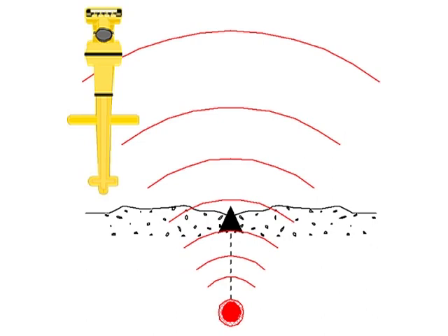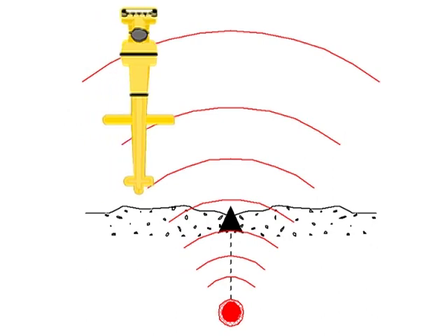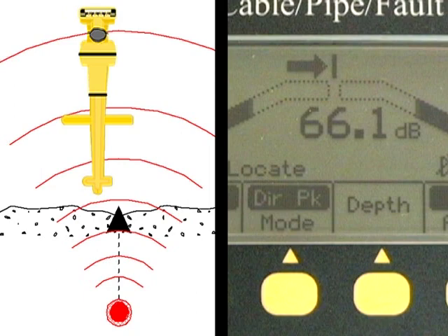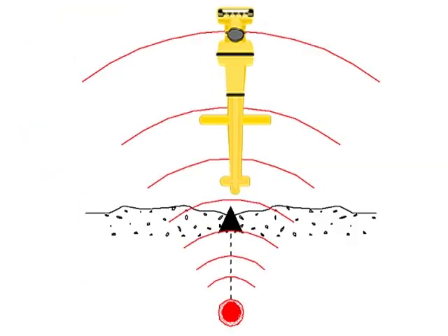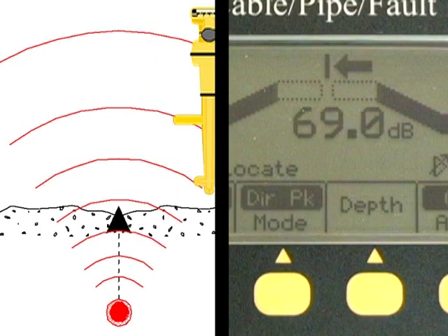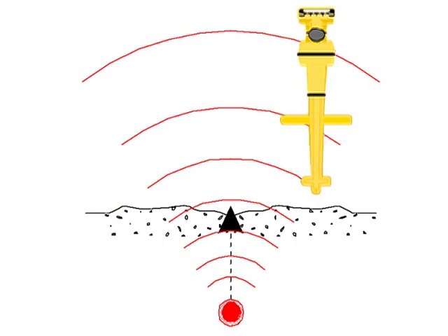As the receiver approaches the electromagnetic field from the left of the target path, an arrow will appear on the locating screen pointing toward the right. It is detecting the rise of the electromagnetic field surrounding the target conductor. As the receiver crosses the path of the target conductor, the arrow pointing to the left will appear, indicating the target has been passed. The crossbar is now detecting the fall of the electromagnetic field.